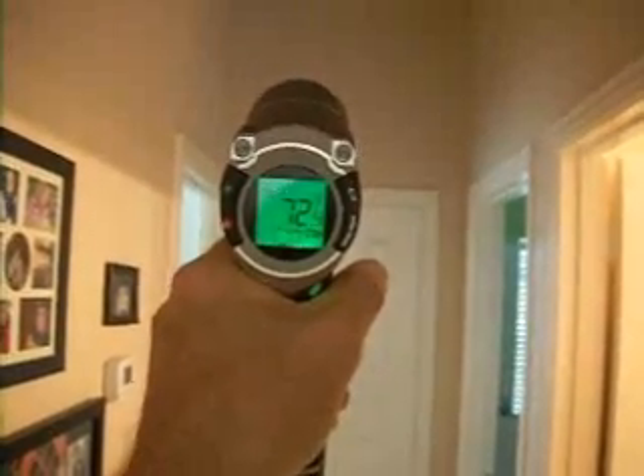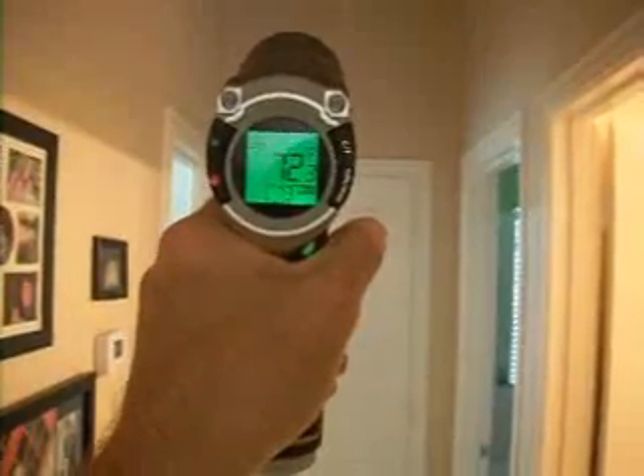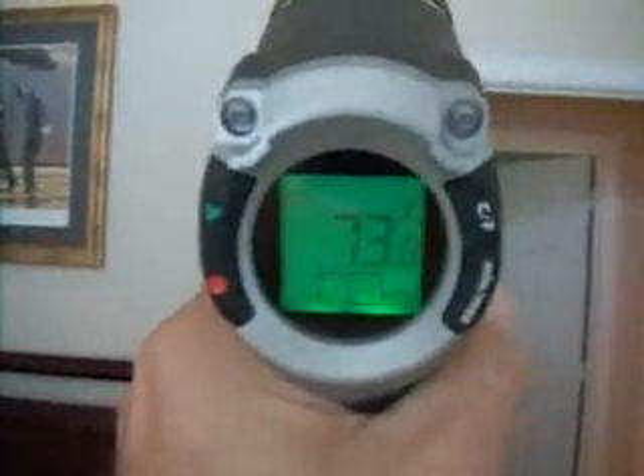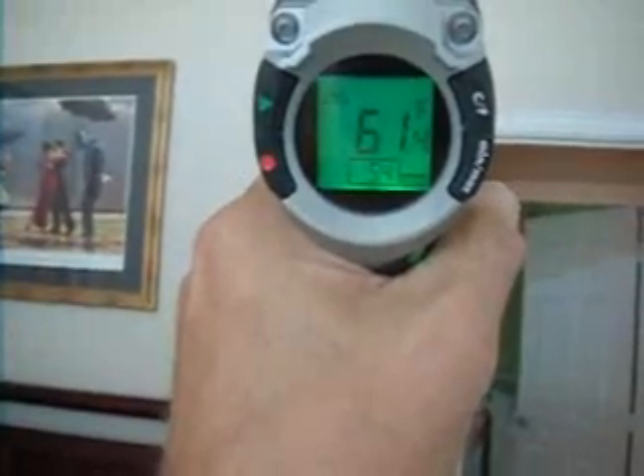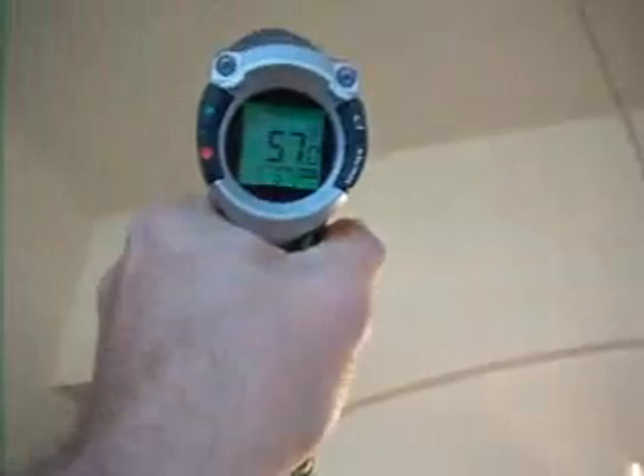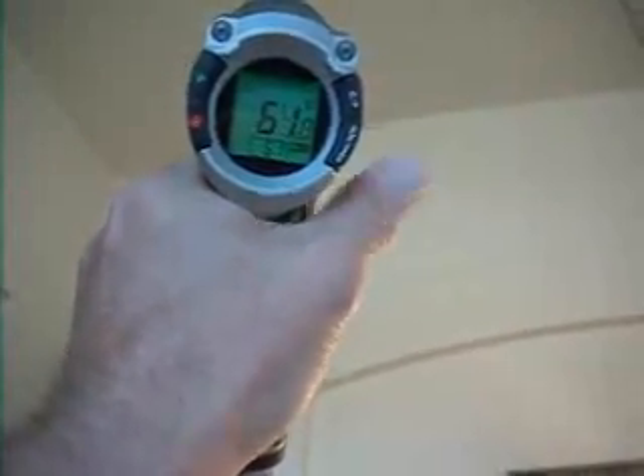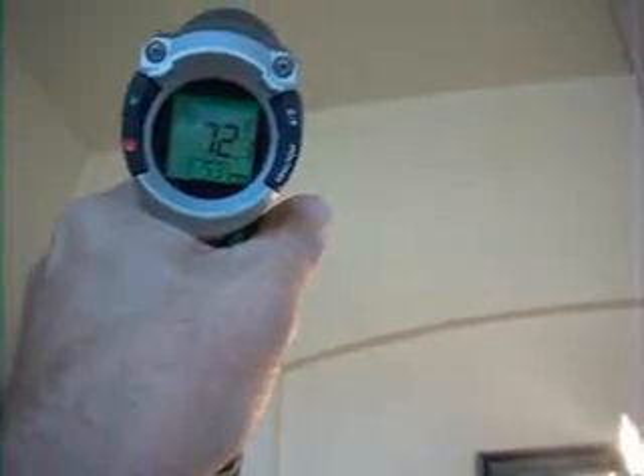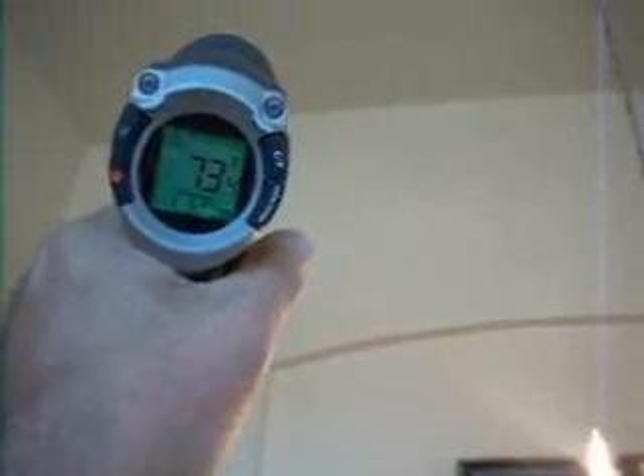This is the assessment of the air conditioning's performance. We've got a return here of 72 degrees, and now what we're going to do is measure the registers and see what temperatures we're getting. Switch to minimum. Here's the register. And on the register here we're getting the minimum temperature of 54. Let's go and look at the other vents. Okay, minimum here of 53. So we're going from 72 to 53. That's 20 degrees, which is good.